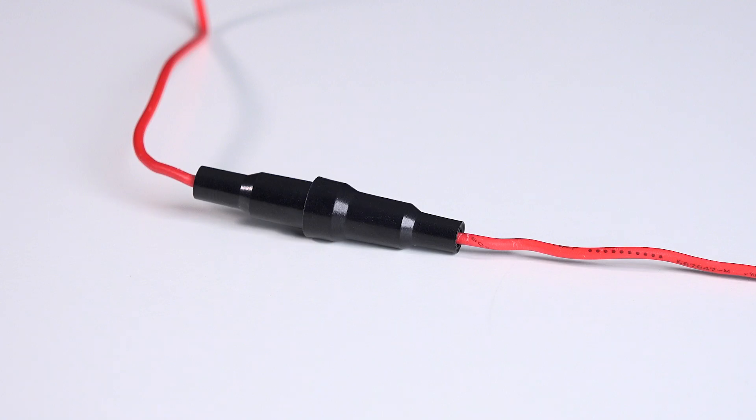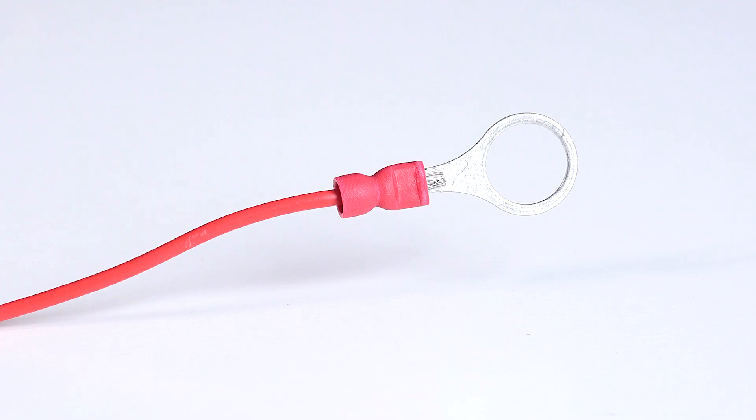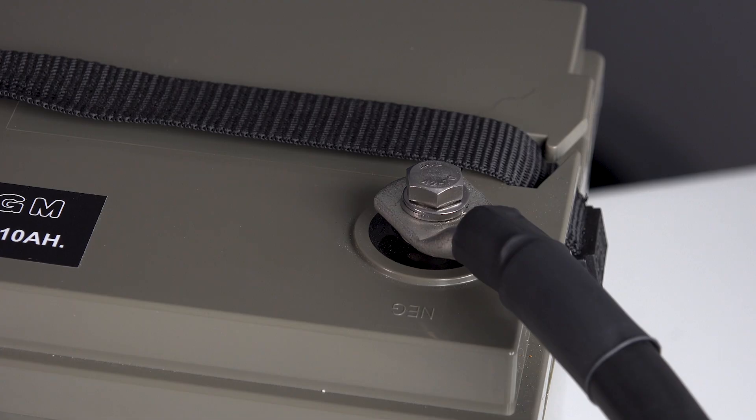I'll connect one of the ferrule pins into the voltage battery plus terminal on the shunt. The other end of the cable has an M8 ring terminal already fitted, so I'll connect that to the negative terminal of the battery. It's vital to pass all negative power through the shunt.